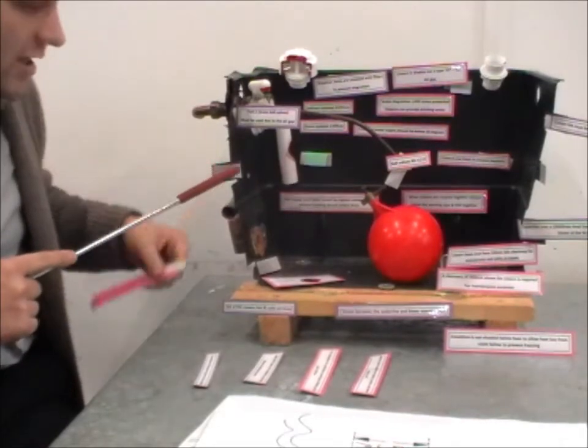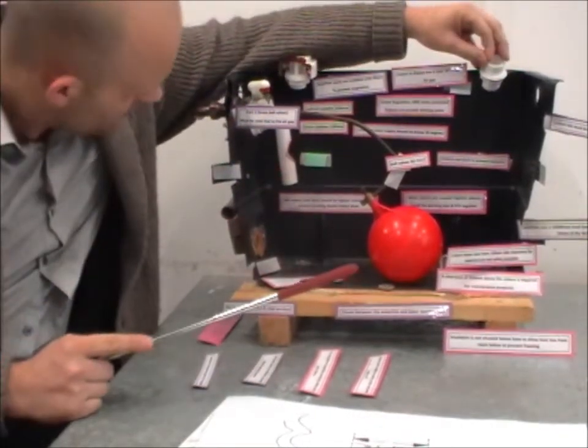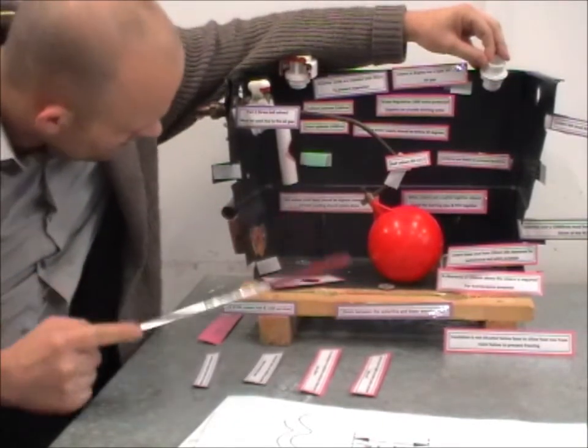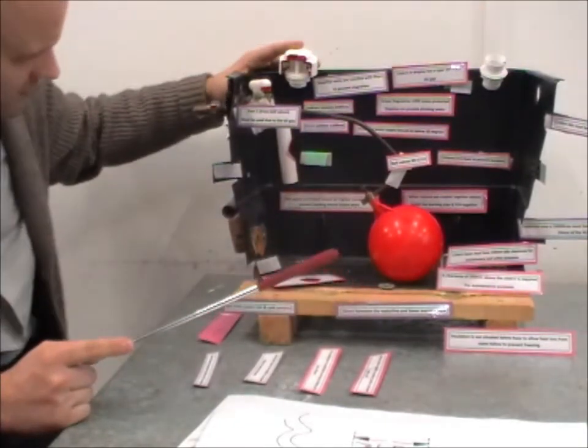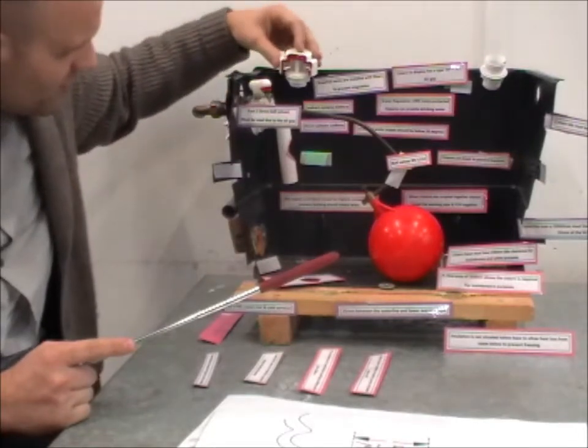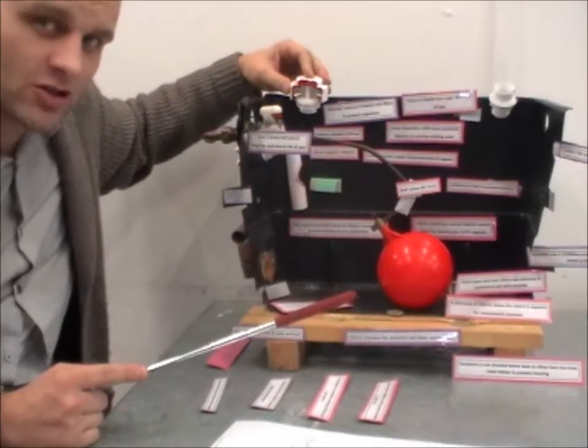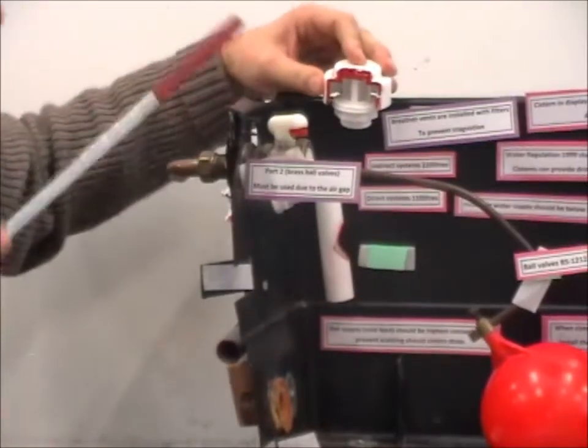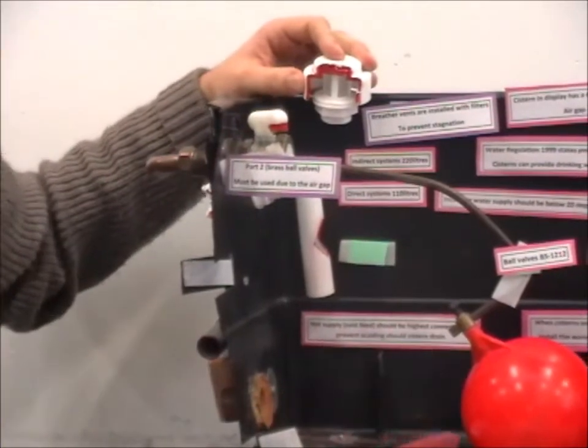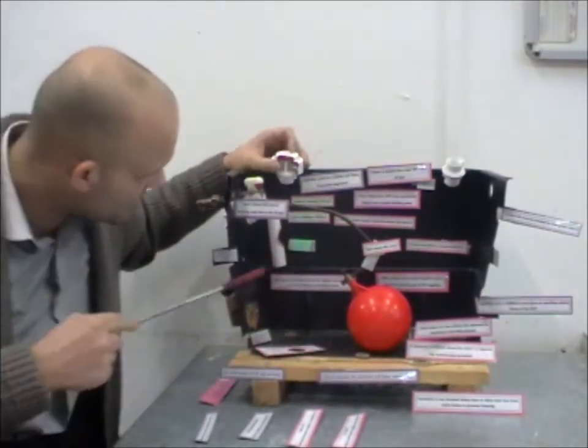Filters should be inside overflow pipes, which is just here. Just here you have a breather vent as well. That's got an overflow screen in as well. So they both have screens in. So we do let air in, but however, we don't let insects or flies inside.